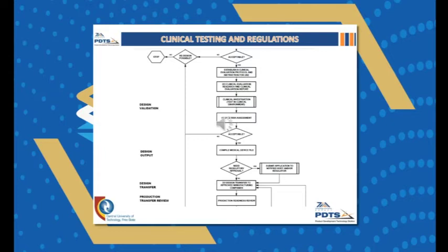All the clinical investigation evaluation is done to verify that the design or the product meets the intended use. This process is basically called the design validation. The design validation process or testing can be conducted in a real or simulated environment to demonstrate that the intended user needs have been fulfilled. As explained earlier, the reason for this is that a product can be technically 100% correct but useless in a real setting. To avoid this, a design validation needs to be conducted.